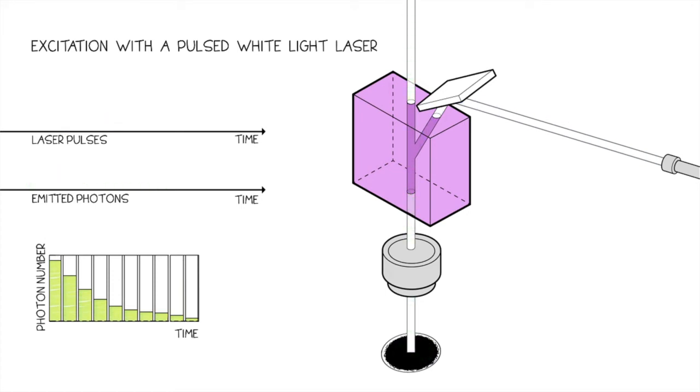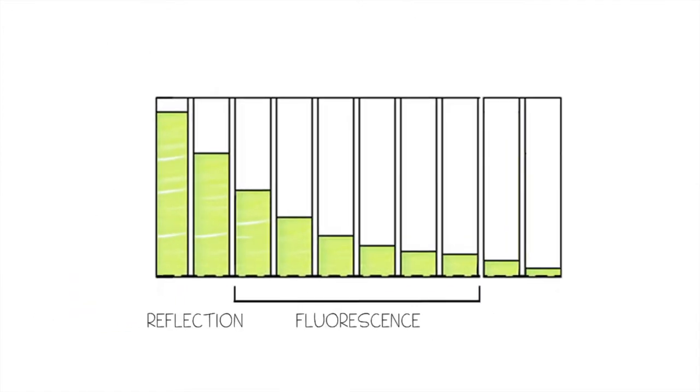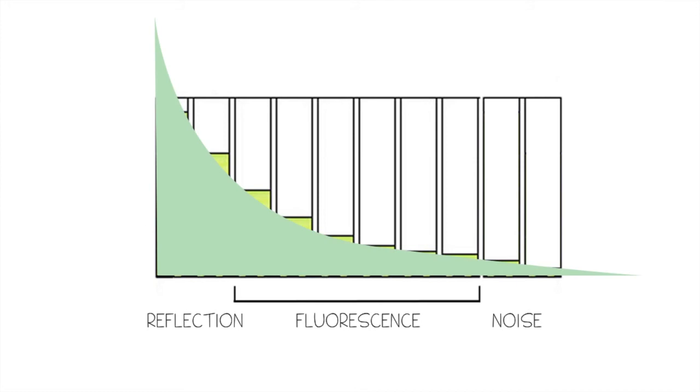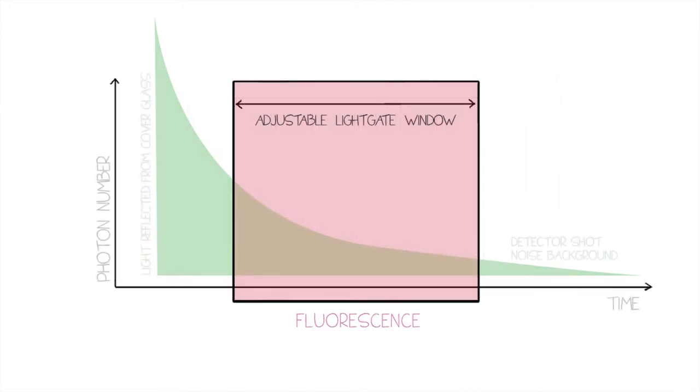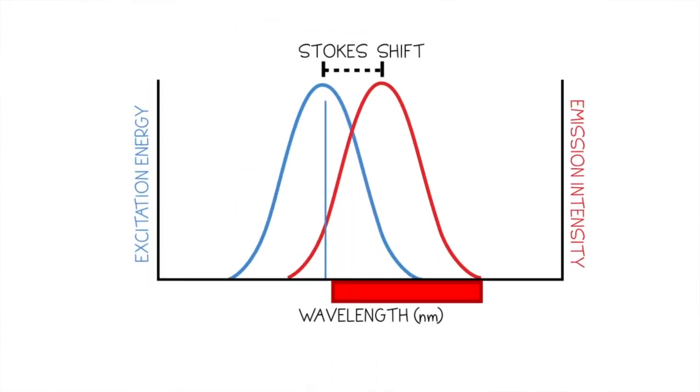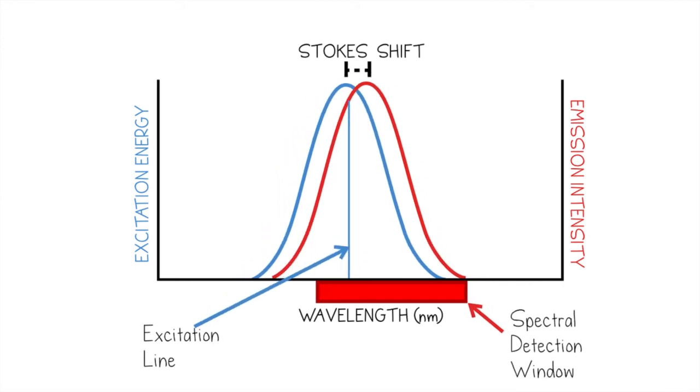For reflections which only occur very early in the pulse, light gate can exclude data from this brief period to prevent it from confounding fluorescent signals and contributing to the image. An additional benefit of light gate is that it maximizes photon harvest, like when working with short Stokes shift dyes, by allowing emission detection over the excitation laser line.